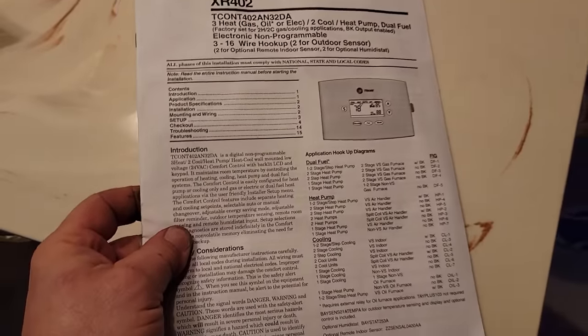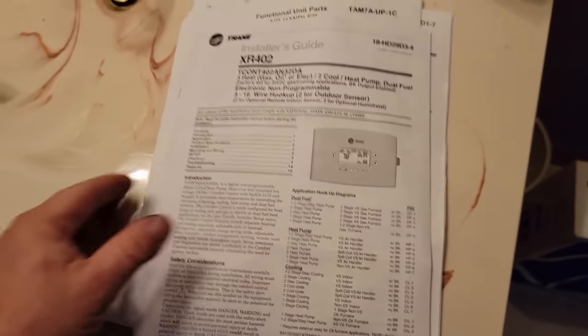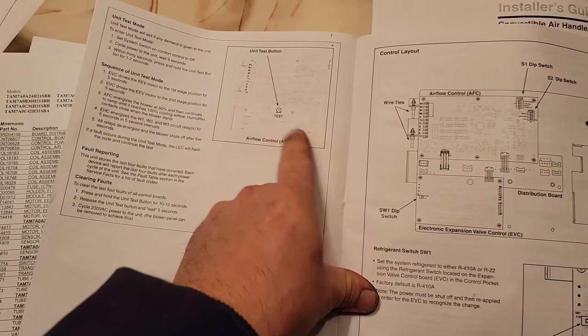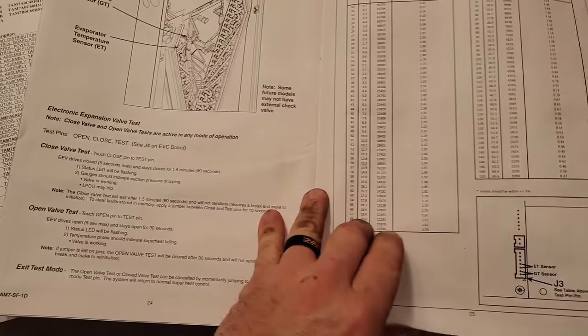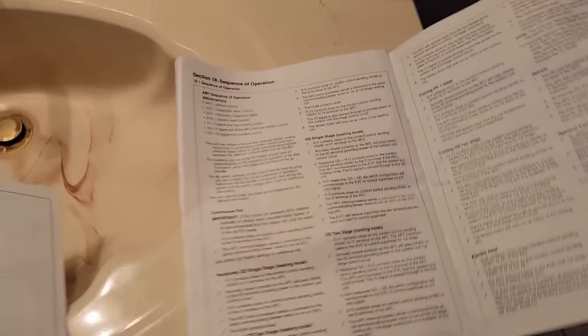Looking at the installer's guide - starting off, I'm going to check for a leak. I can almost guarantee right now we're low on refrigerant and we have an airflow issue. There's a test button and a gas temperature sensor. A nice thing is you can see the condenser coil is right out there, less than three or four feet from the unit.